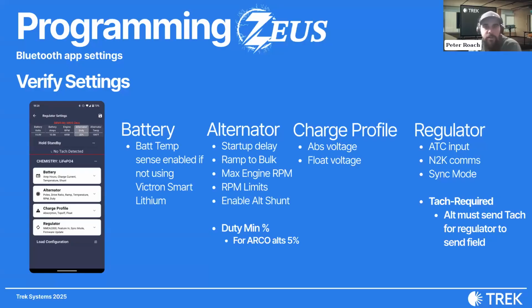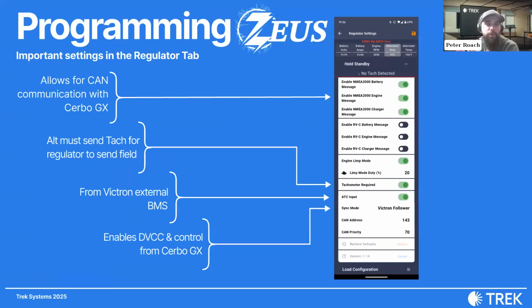In the charge profile, this is where we set the absorption voltage and float voltage of the battery. On the regulator tab, we're going to enable the ATC input. This is also where the NMEA 2000 and RV-C communications are, as well as the different sync modes, the follower modes, and we'll be setting Victron follower in our case. We're going to go over a few important settings on the regulator tab. For the CAN communication to the Cerbo GX, we want to enable all three NMEA 2000 messages, as you see in the image to the right. This will set up the communication for the system. And like I was just saying, make sure to enable TAC required. This ensures that charging will not begin until a TAC signal is received.